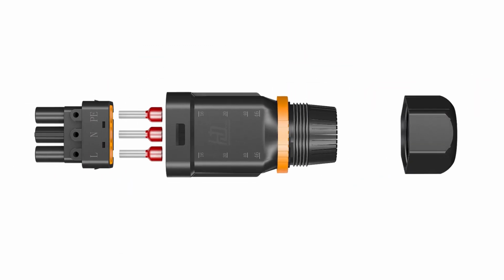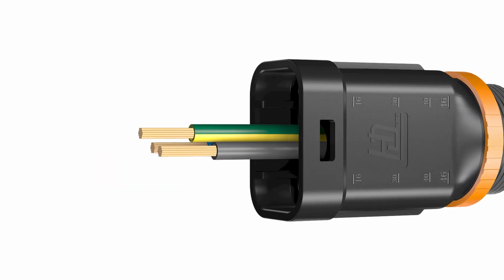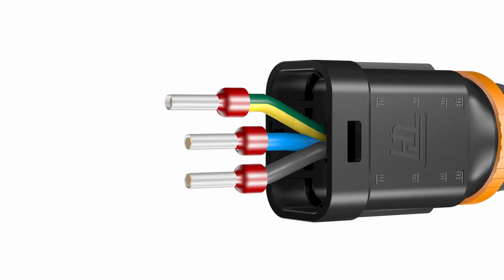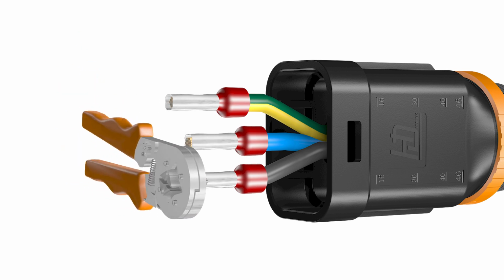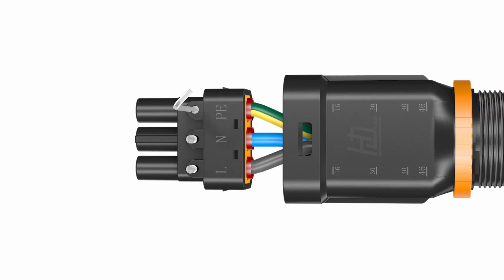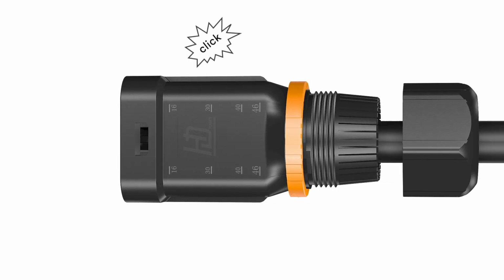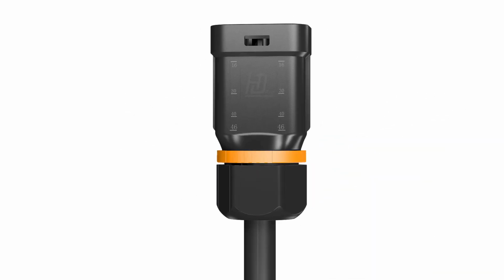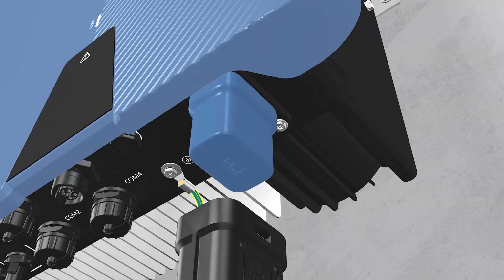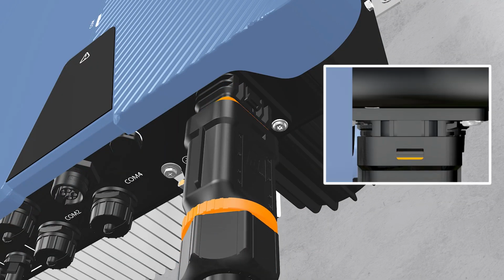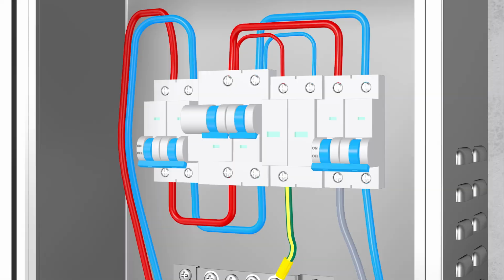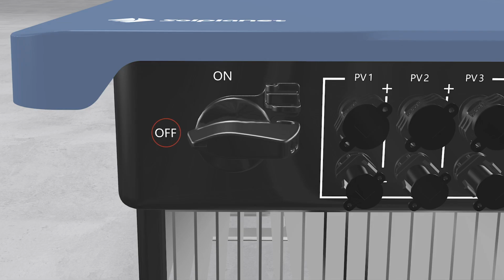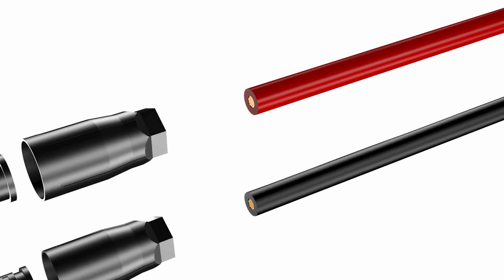Loosen the swivel nut of AC connector. Insert the crimped conductors into corresponding terminals and tighten screws with the accompanied Allen key. Insert the adapter to the socket element, stuff the seal ring into the adapter and tighten the swivel nut. Disconnecting the PV array. Make sure the AC circuit breaker is disconnected and the DC switch is in the off position before stripping off the cable insulation.